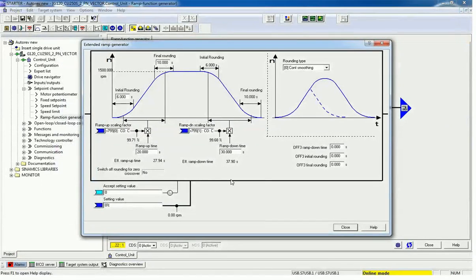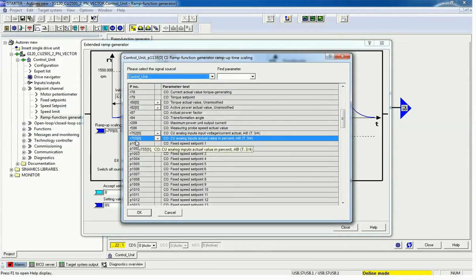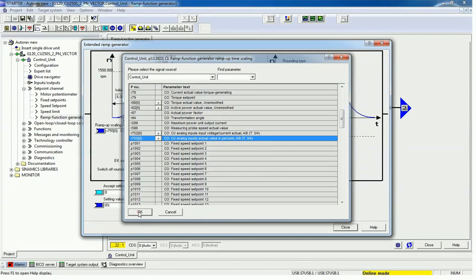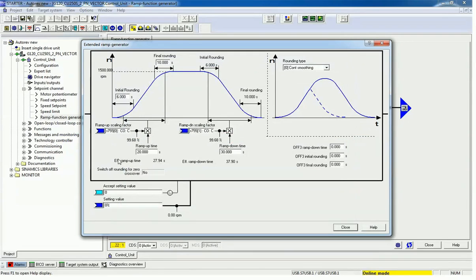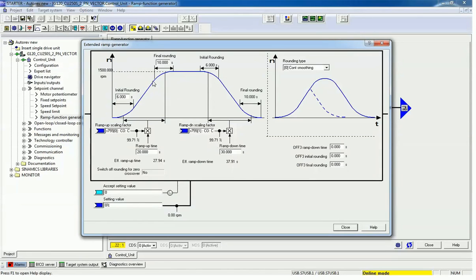I have configured one analog input. You can go for further interconnection using parameter number R755 — you can configure analog input 0 here, and I configured analog input 1. You can give ramp up time and ramp down time as per your requirement or load. I have given initial rounding and final rounding time, and as per the equation we will get the effective ramp up time.